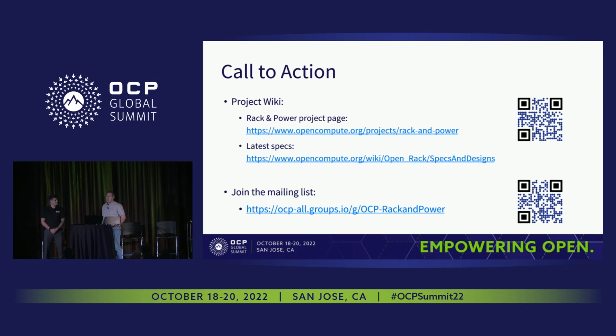Another thing to consider is as we're moving these racks around within the data centers, we still want to make sure we have that cross brace providing stiffness of the frame. We've got a lot of expensive gear in our racks, and we definitely don't want gear delatching—it potentially introduces damage to the gear and creates a safety hazard for personnel moving those racks around. So we want to maintain that stiffness of the rack as it's deployed.